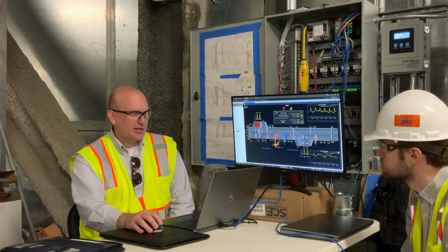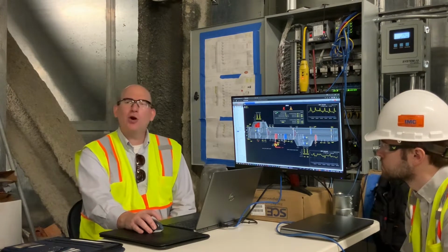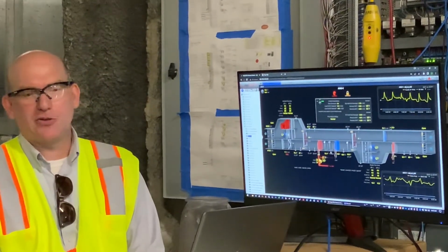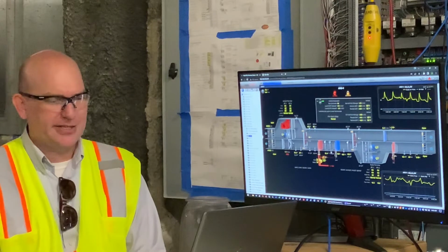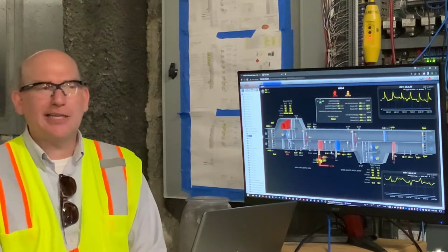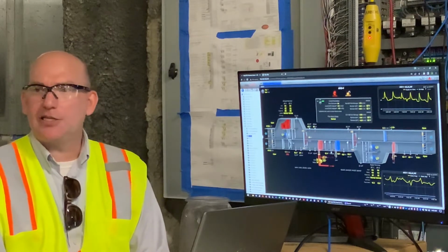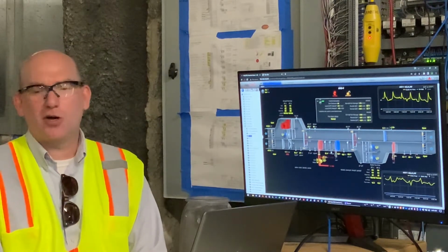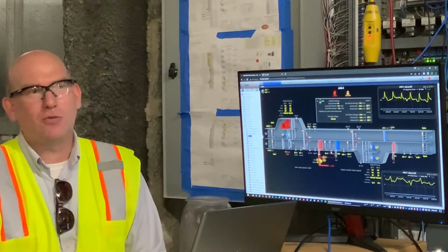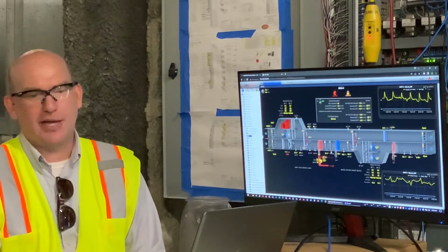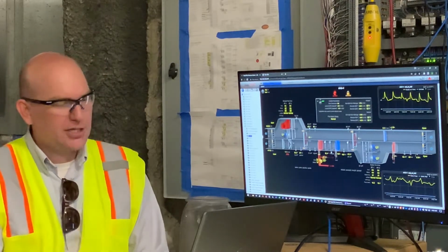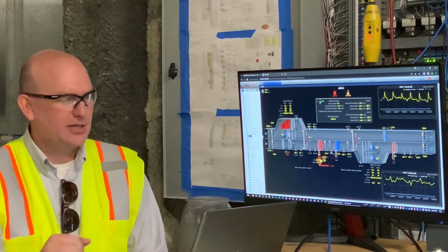So safety-wise, when we take a look at one of these enclosures, we'll point out those safety relays and where they all exist. All of these things are hardwired to an individual relay. It makes it the easiest to troubleshoot. It also makes it the easiest to test. If you want to test how it works, you literally go up to the relay, pop it out, and it'll perform the action that you would expect it to. We'll see that when we walk over and take a look at the can.